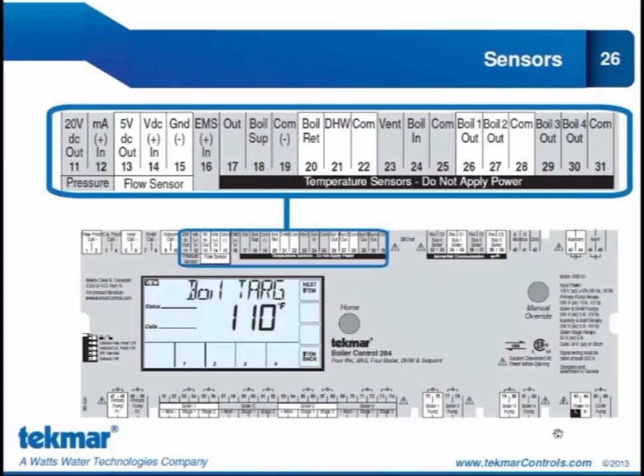Here are the sensor input terminals, and there are a lot of them. We can connect our pressure sensor and our flow sensor here. We have our EMS input, and this is what's nice on the 284. On the other controls, the older controls, the EMS input had to go through the outdoor sensor terminals, and now we have dedicated terminals for the EMS input. We have terminals for our boiler supply sensor, our boiler return sensor, domestic hot water sensor, and you can see here it's not labeled IDHW or DDHW because we can connect a domestic hot water sensor in either dedicated domestic hot water or indirect domestic hot water operation.